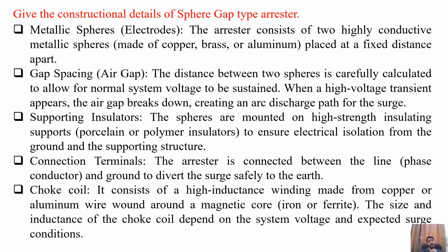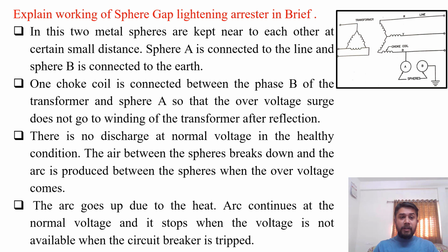It consists of a high inductive winding made from copper or aluminum wire wound on a metallic core, that is, an iron or ferrite core. The size and inductance of the choke coil depend on the system voltage and the expected surge conditions. So these are some constructional details of the sphere gap type arrestor. We have already seen the diagram for the same while we are discussing the brief operational detail of the sphere gap type arrestor. Explain working of sphere gap lightning arrestor in brief.